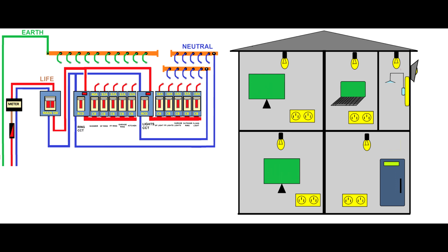Now imagine you have a home, and like I said in the last video, you come home very tired from work, and for some reason there is very heavy rain outside, and we have a big variation in temperature, and the floodlight, even if it's IP65, is still sweating inside, and if the water touches open electrical wire, it will create a kind of earth leak or short circuit. So the RCD under this condition will trip.